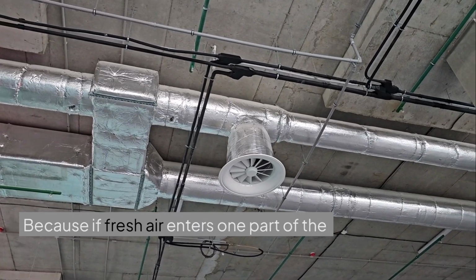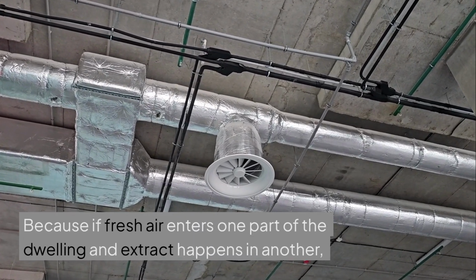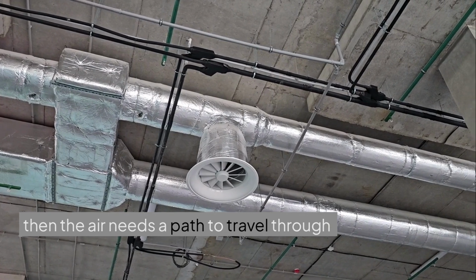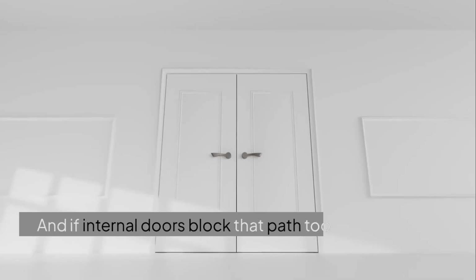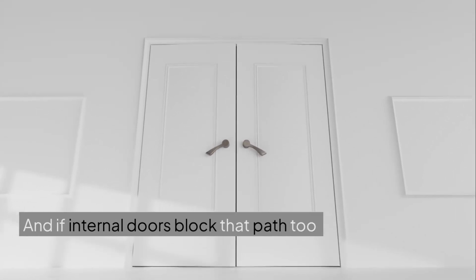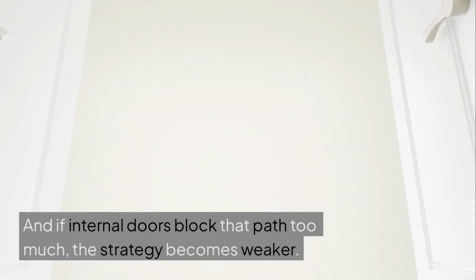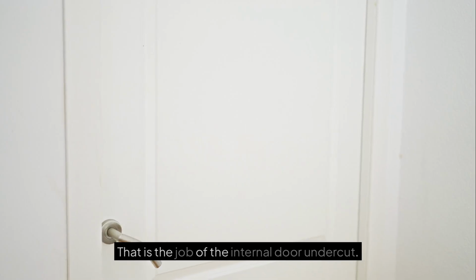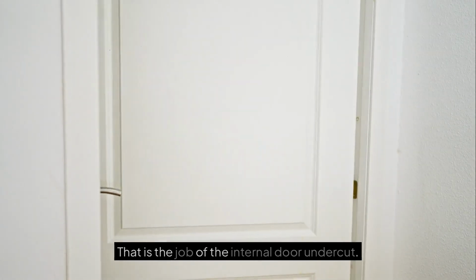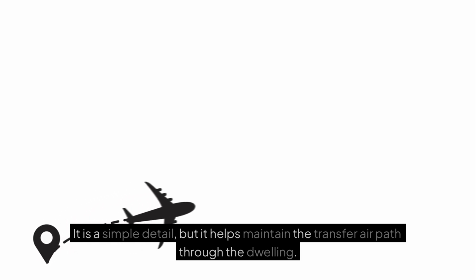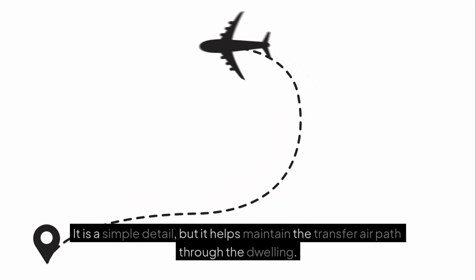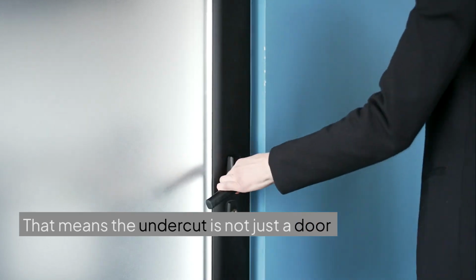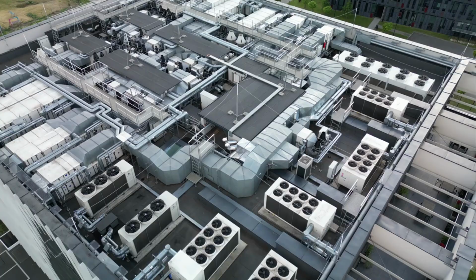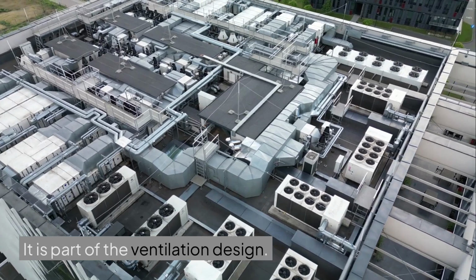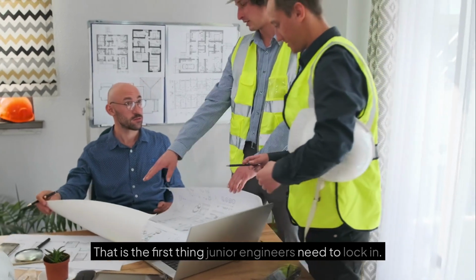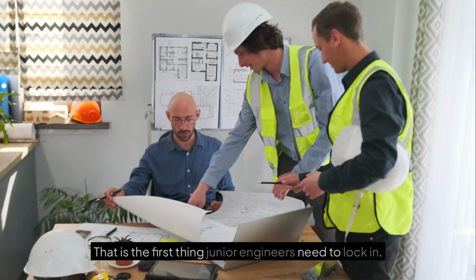Because if fresh air enters one part of the dwelling and extract happens in another, then the air needs a path to travel through the home. And if internal doors block that path too much, the strategy becomes weaker. That is the job of the internal door undercut. It is a simple detail, but it helps maintain the transfer air path through the dwelling. That means the undercut is not just a door detail, it is part of the ventilation design. That is the first thing junior engineers need to lock in.